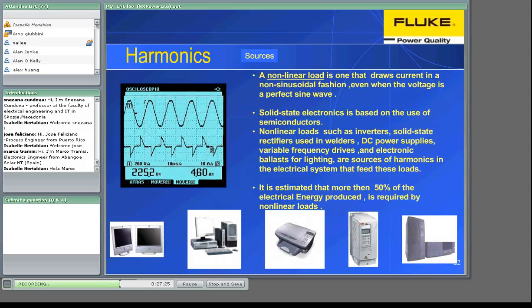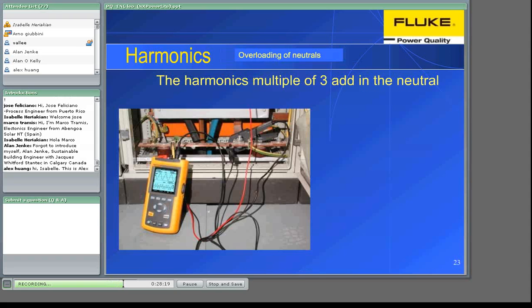PC-type loads are characterized by being rich in all the low-order harmonics, with very high content or level of the third, the fifth, the seventh, and the ninth harmonic. Electronic lighting ballasts have become popular for improved efficiency. Again, the drawback consists in the generation of harmonics in the supply current. Speed controllers, UPS, and DC converters are also known as harmonic producers. Finally, it is estimated that more than 50% of the electrical energy demand comes from nonlinear loads. So you can imagine the influence of nonlinear loads on the quality of the product called electricity.